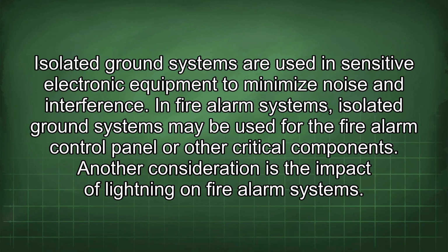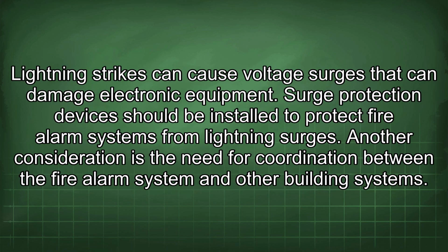Another consideration is the impact of lightning on fire alarm systems. Lightning strikes can cause voltage surges that can damage electronic equipment. Surge protection devices should be installed to protect fire alarm systems from lightning surges.